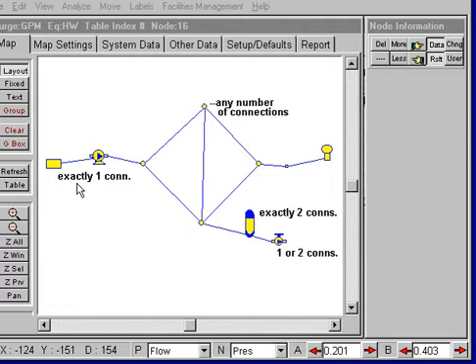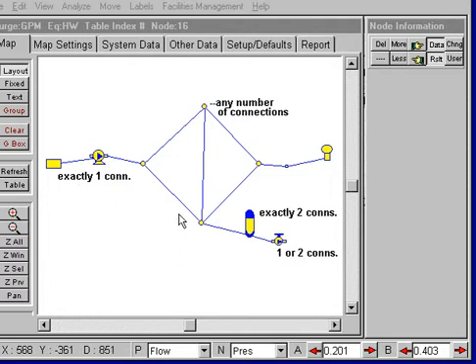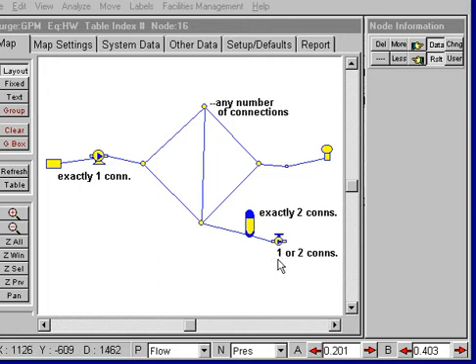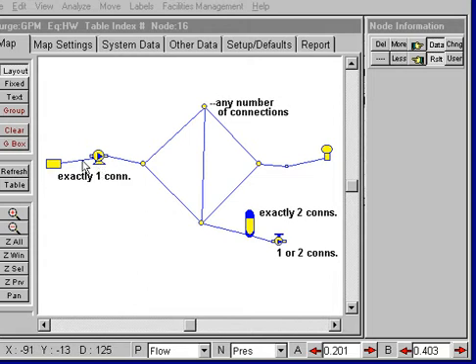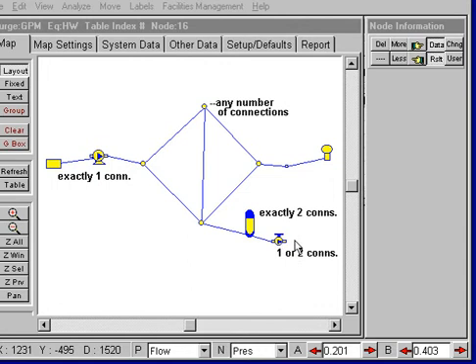For components such as pumps, valves, sprinklers, we can have one or two connections. Now, if we have two connections, there'll be one to either side. If we have one connection, it's assumed that the second side is at a reservoir and we'll have to provide data for that reservoir.